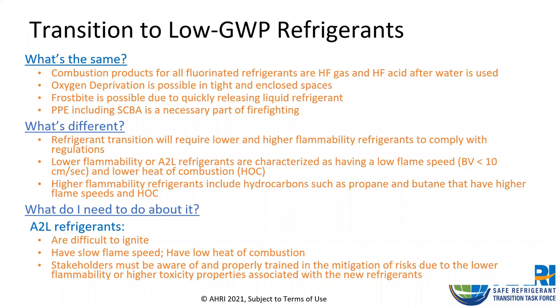These refrigerants really are very difficult to ignite. Some of the higher flammability refrigerants, including hydrocarbons such as propane and butane, have higher flame speeds and higher heat of combustion. But again, they're also successfully being used in certain applications. So what do I need to do about this transition?